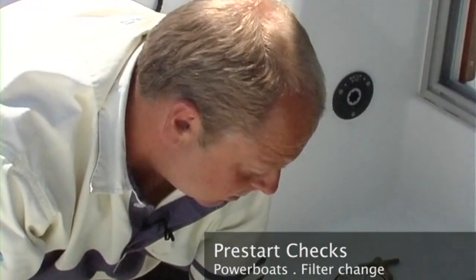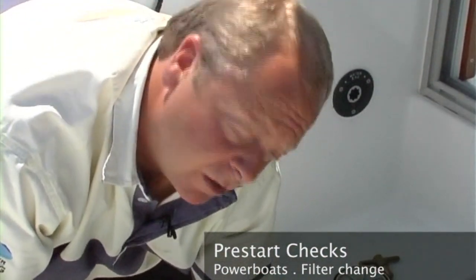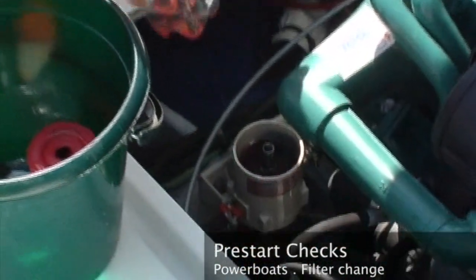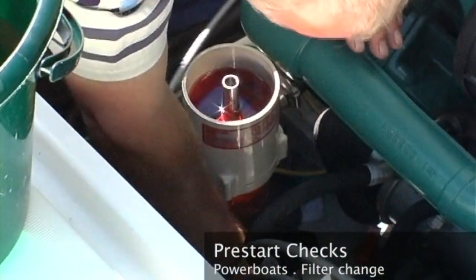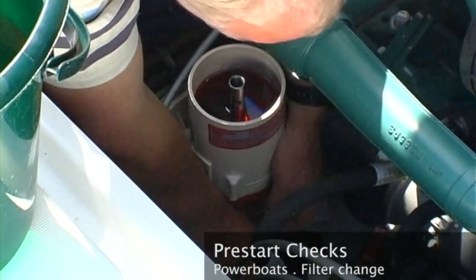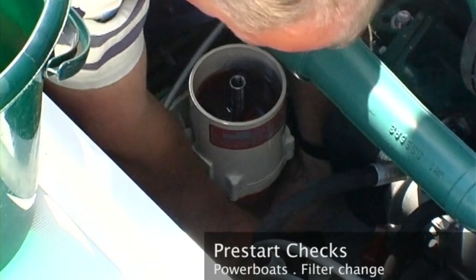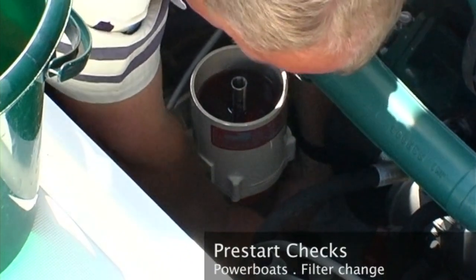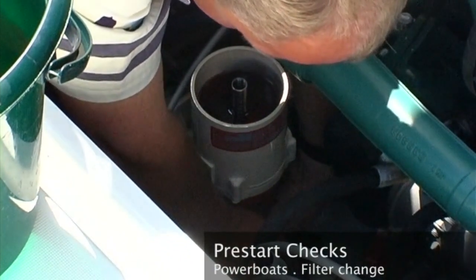Now if we found dirt or muck in the filter, we'd want to drain all this diesel out before we put back the new filter. So with the lid off, place a container of suitable size to take the amount of fuel. Open the drain cock again.